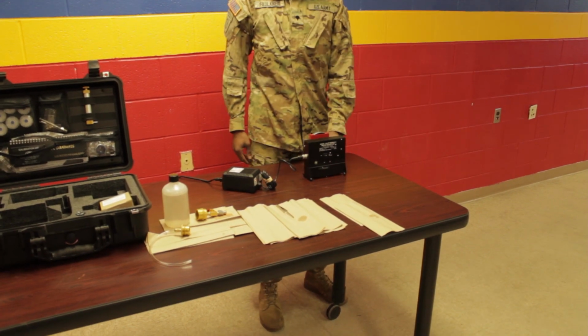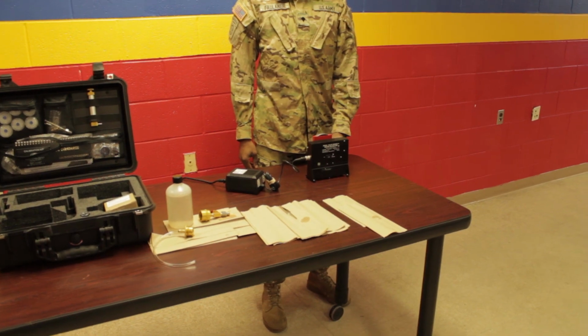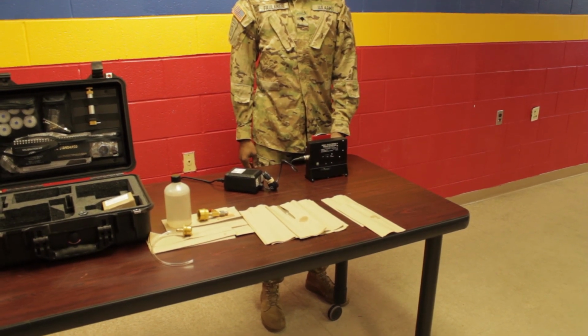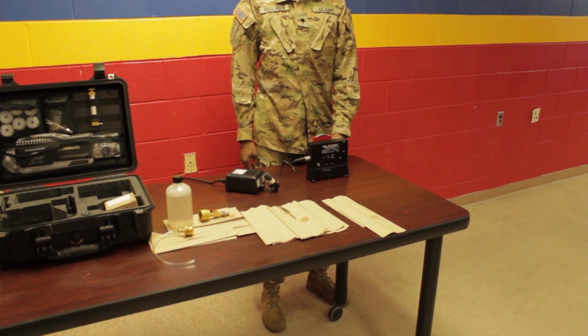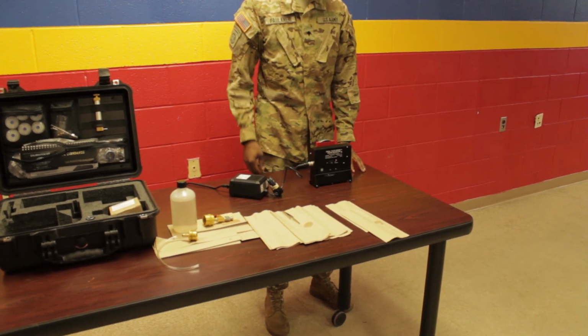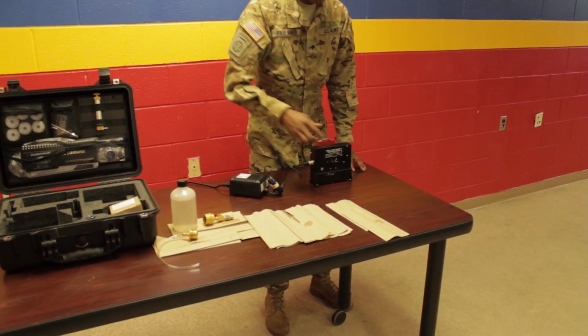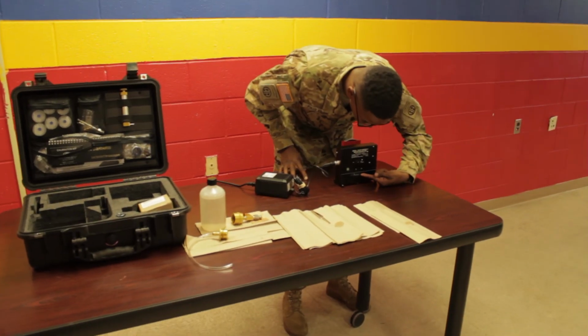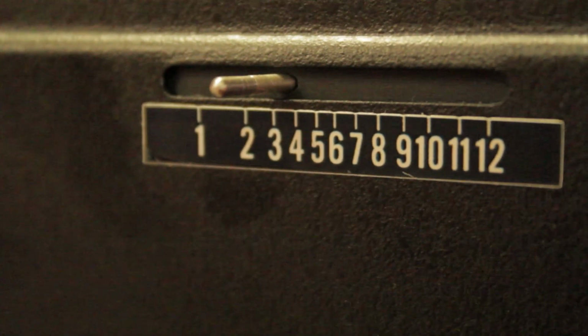If the reading is more than 10 parts per million, recirculate and retest. If the retest shows more than 10 parts per million of water, submit a sample to the supporting laboratory for inspection and disposition instructions. Then take the fuel and fueling equipment system out of service.